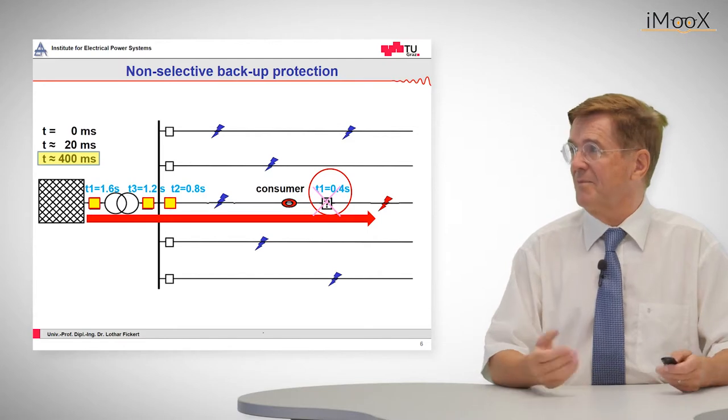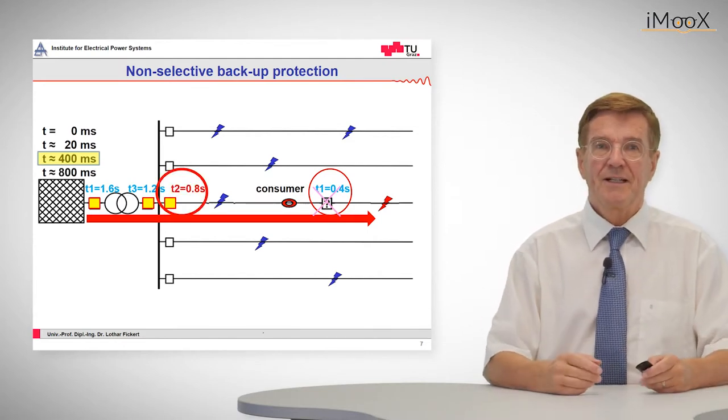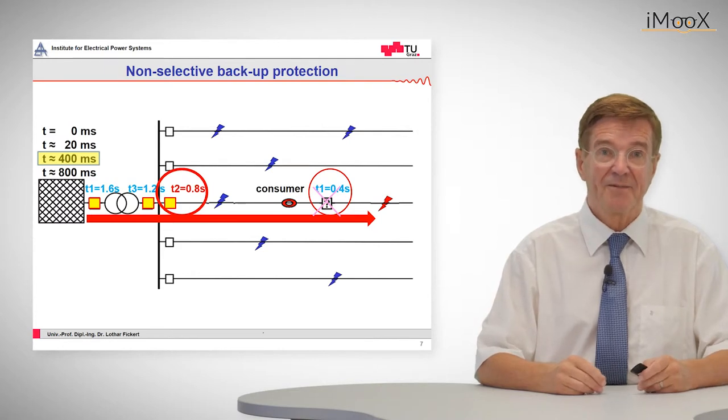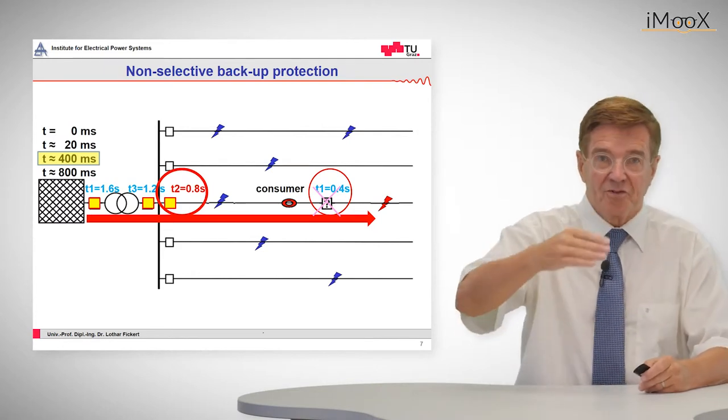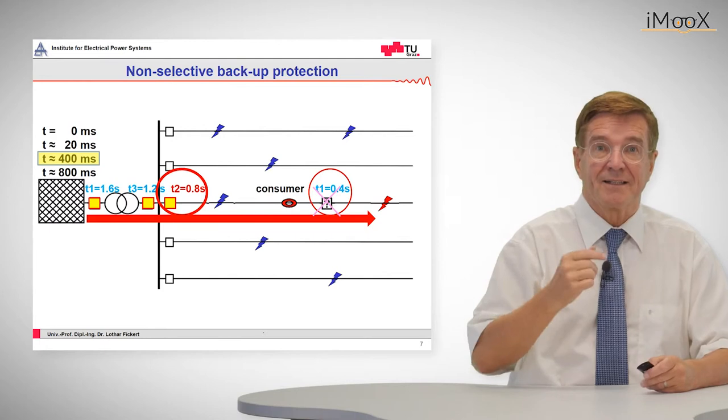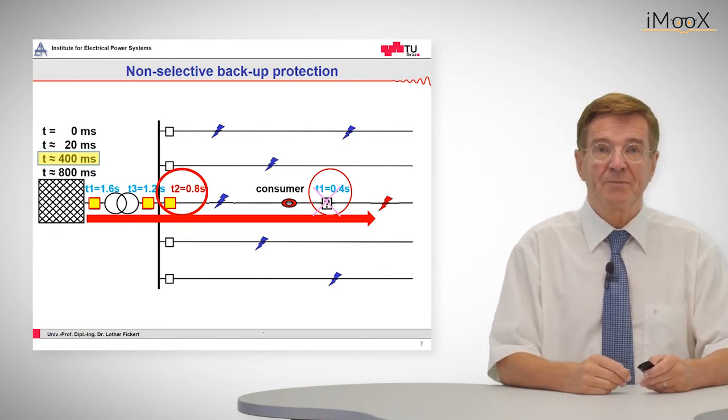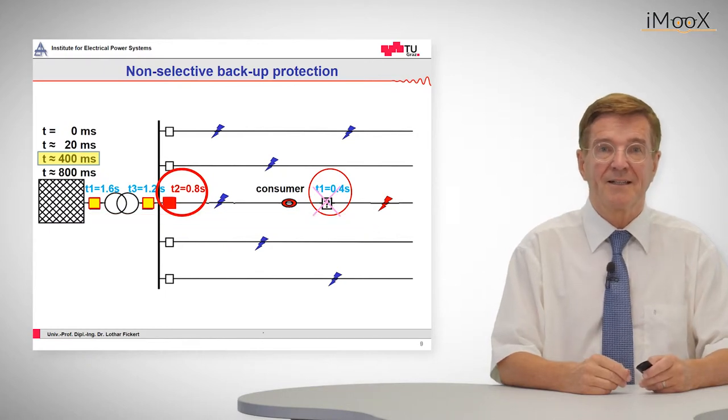So what happens? Somehow it does not work and it will not trip after 0.4 seconds as indicated. Then the time goes on and a short time later at 0.8 seconds, the next upstream relay will pick up and clear that fault.